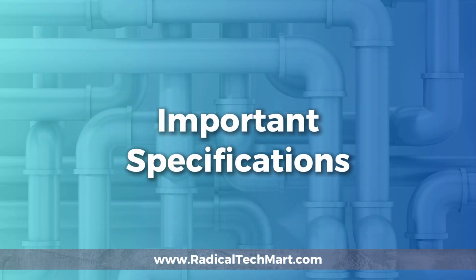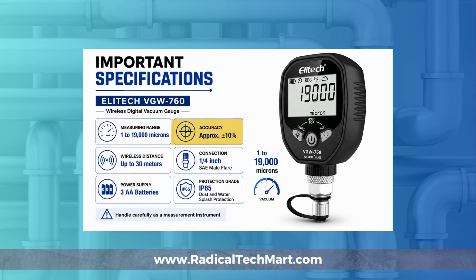The measuring range is 1 to 19,000 microns. The accuracy is approximately plus or minus 10%. Wireless transmission distance is around 30 meters. The fitting is a 1/4 inch SAE male flare, which is common in HVAC and refrigeration service work. It uses 3 AA batteries. The protection grade is IP65, which gives protection against dust and water splash in normal use. But still, it should be handled carefully as a measurement instrument.